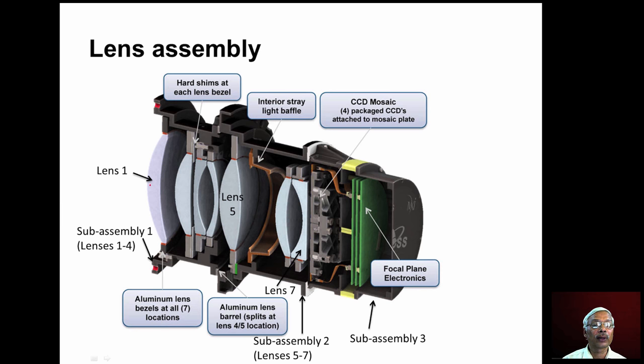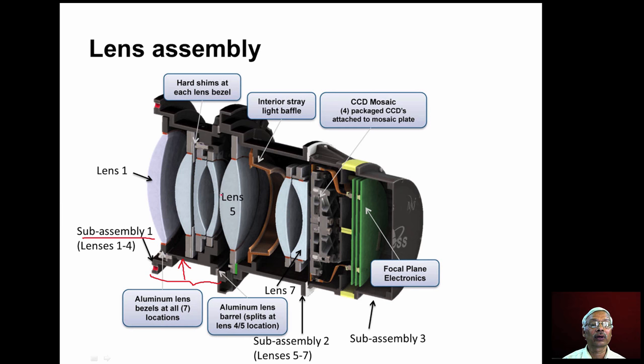Lenses one to four form sub-assembly number one. This is a split barrel. We have retainer rings to retain each lens, and between two retainer rings we have shim plates for adjusting the axial alignment of lenses.